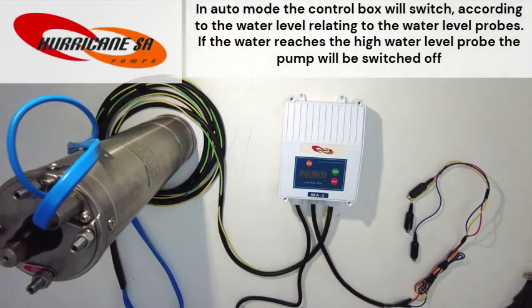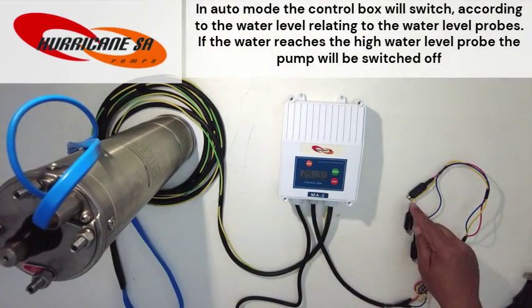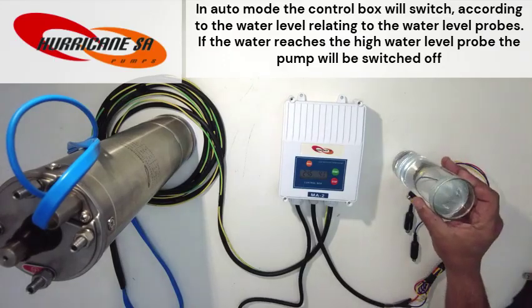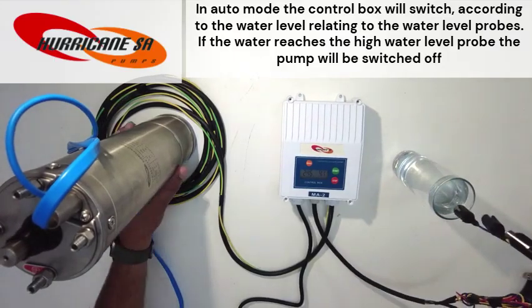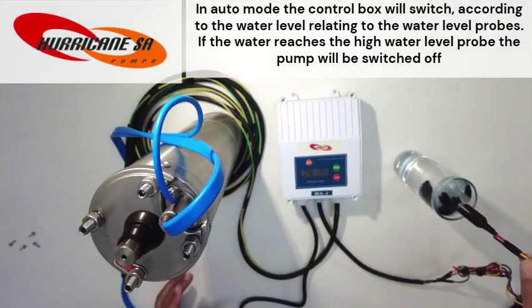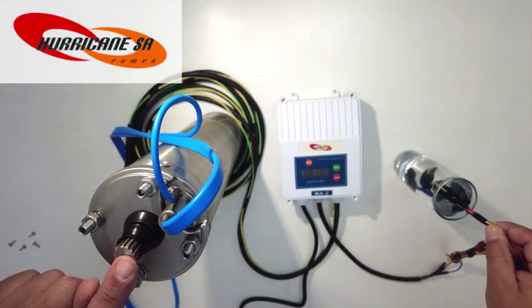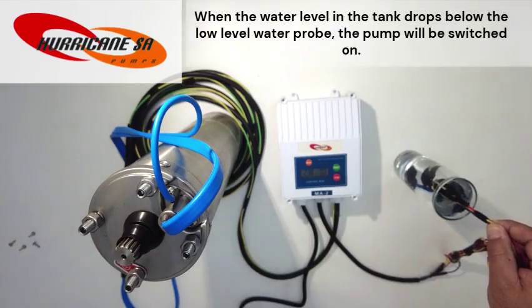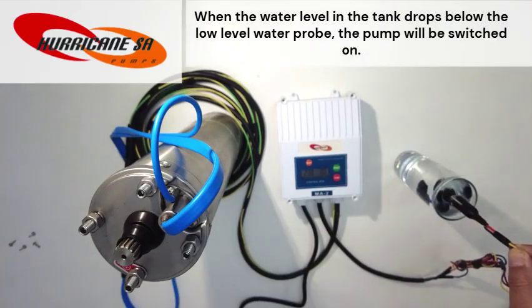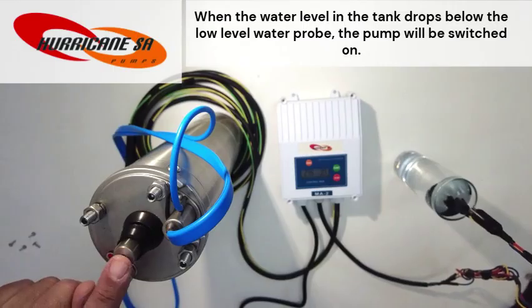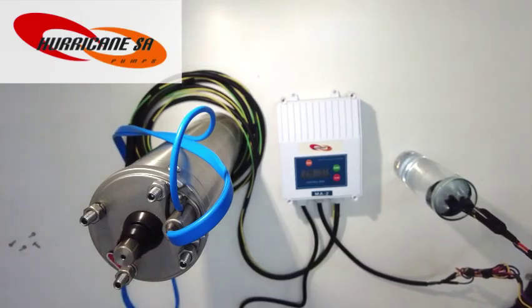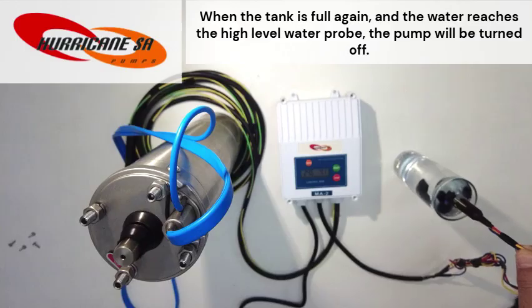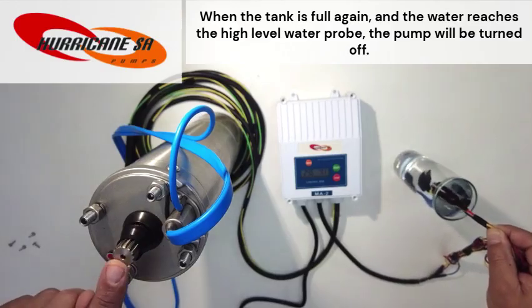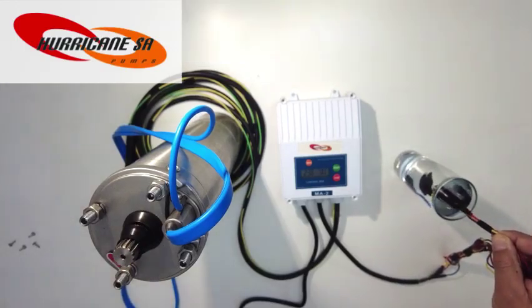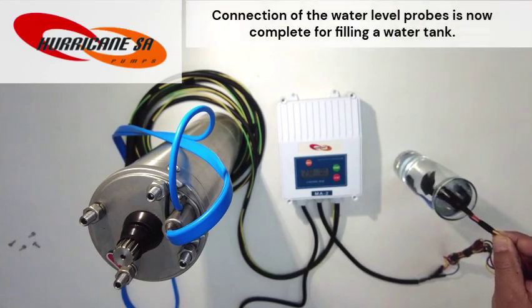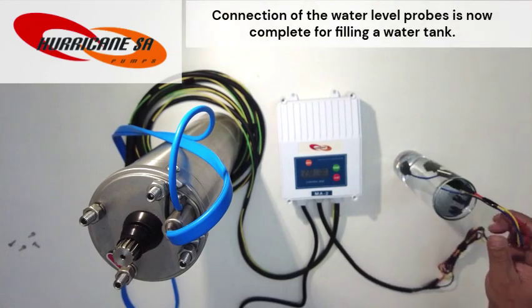In auto mode, the control box will switch according to the water level relating to the water level probes. If the water reaches a high water level probe, the pump will be switched off. When the water level in the tank drops below the low level water probe, the pump will be switched on. When the tank is full again and the water reaches a high level water probe, the pump will be turned off. Connection of the water level probes is now complete for filling a water tank.